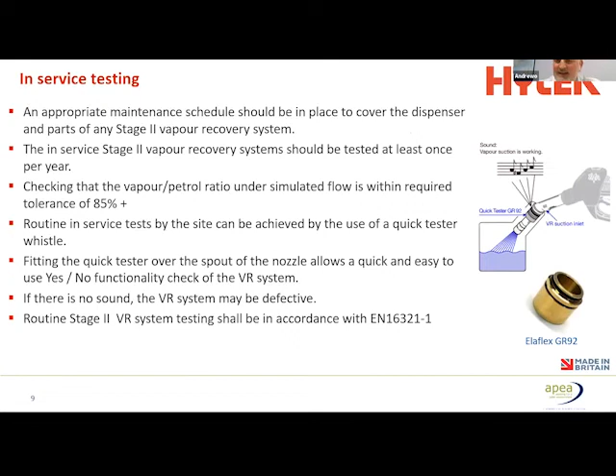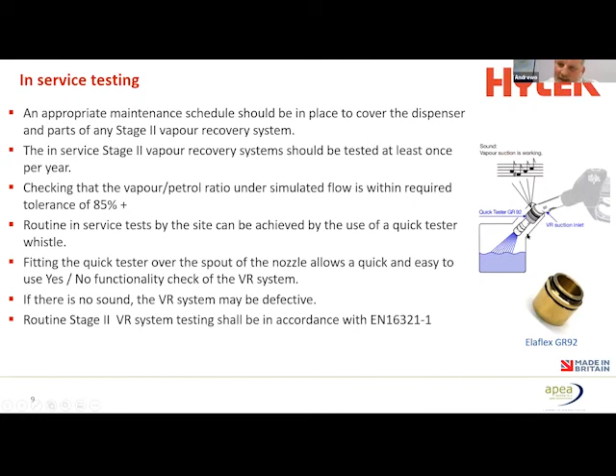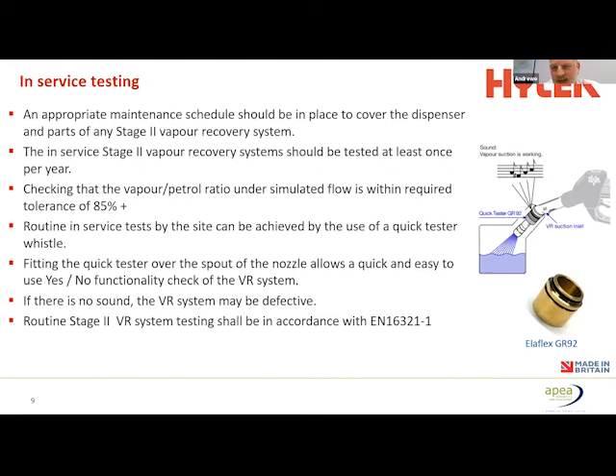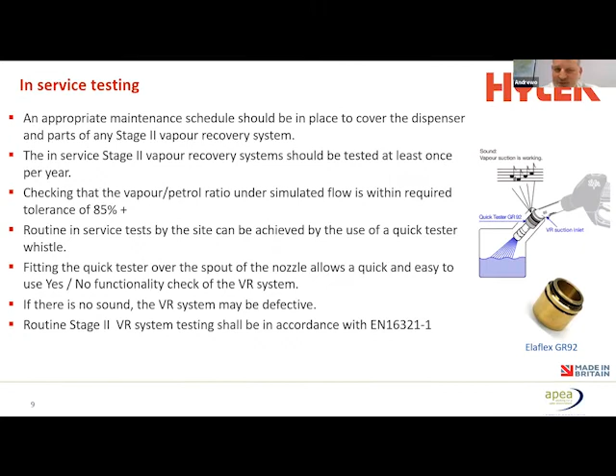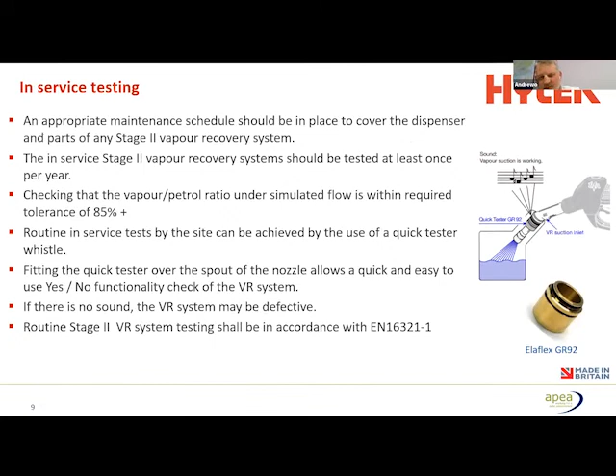We can also look at routine service testing on the site by using a little quick tester, which is like a little whistle. This unit here is put across the end of the nozzle on the stage 2 spout. As the vacuum pump is drawing vapour through, the movement of air is giving you a sound or a whistle. So that then gives you a yes or no function within the VR system. So if there's no sound, that means your VR system is defective. That just confirms that the vapour recovery system is working, but it doesn't confirm that you're meeting the 85% plus.